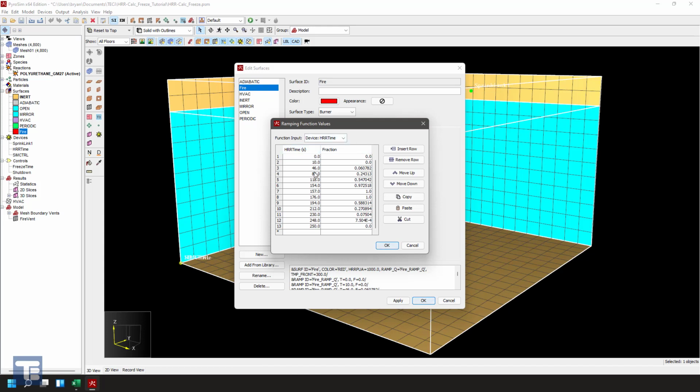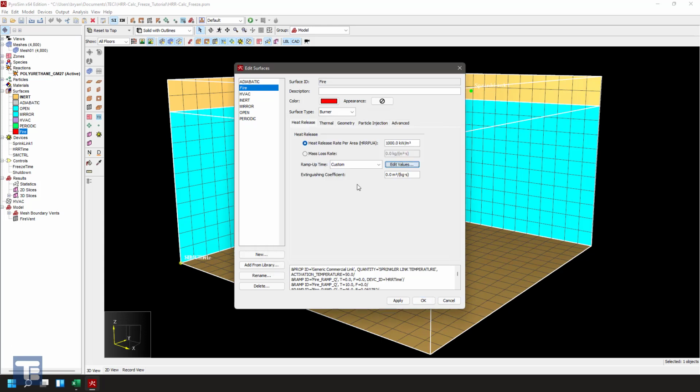And so as it's going up, as soon as the sprinkler link activates, let's say that happens at 90 seconds, then whatever this fractional value in that linear interpolation will be between 82 and 118, when it's at 90, it'll just hold that fraction and just keep it. And it'll keep reporting 90 for the rest of the simulation. And so that'll hold the fraction, this constant, and we'll get a leveling or a flattening of the curve.